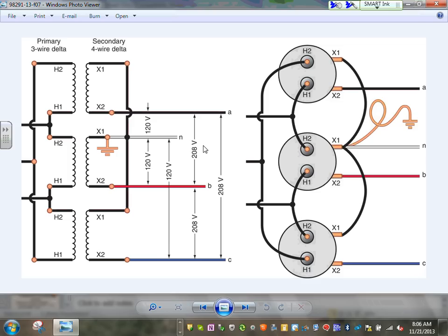Yes, go ahead, Adam. So on that picture, the high voltage, show me where the three phases are going. Where are they coming in? Okay, so phase A, phase B, phase C coming in, and phase A, phase B, phase C coming out. Make sense? Yeah. That's the high voltage. That will be the 13,800 volts coming in on this side, and this side will be 208/120 or 480, whatever you want it to be. Good point. But so easy.